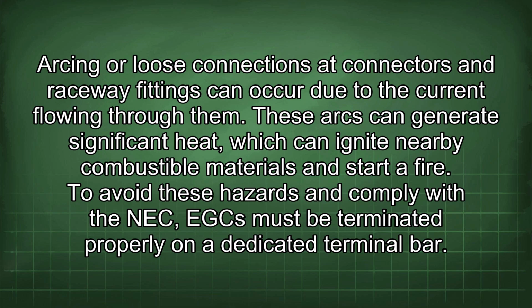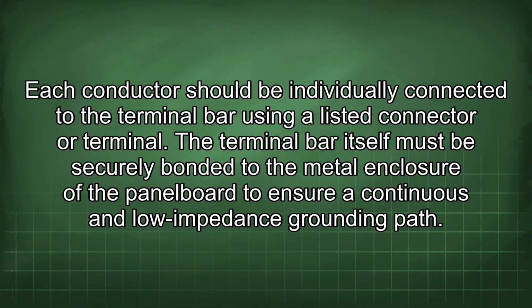To avoid these hazards and comply with the NEC, EGC must be terminated properly on a dedicated terminal bar. Each conductor should be individually connected to the terminal bar using a listed connector or terminal. The terminal bar itself must be securely bonded to the metal enclosure of the panel board to ensure a continuous and low impedance grounding path.